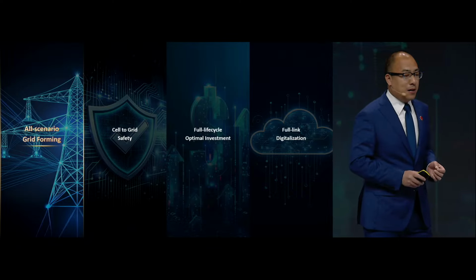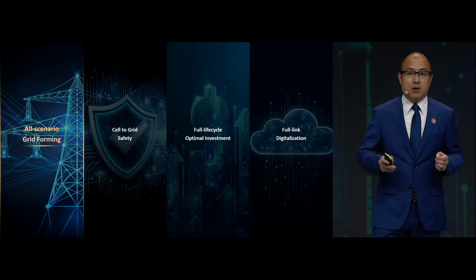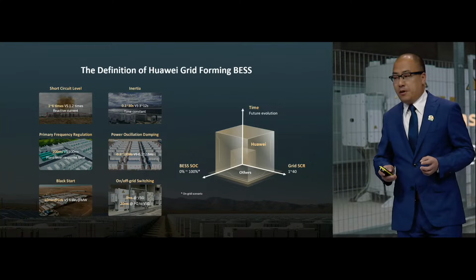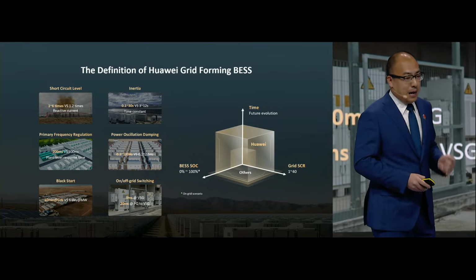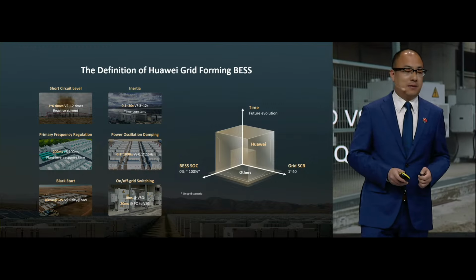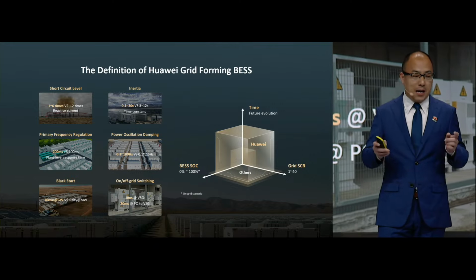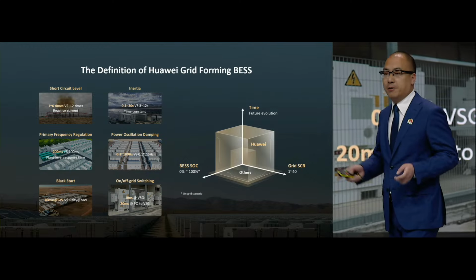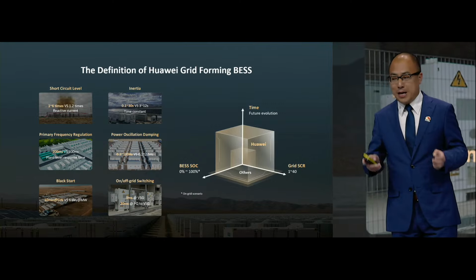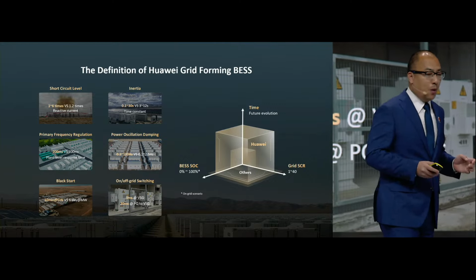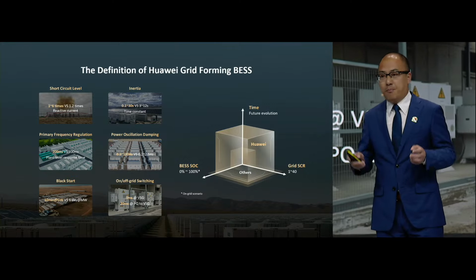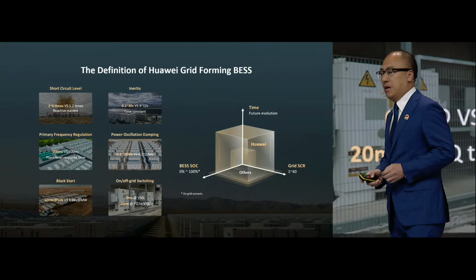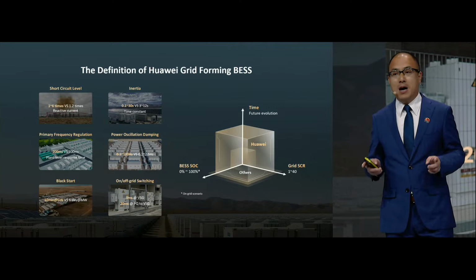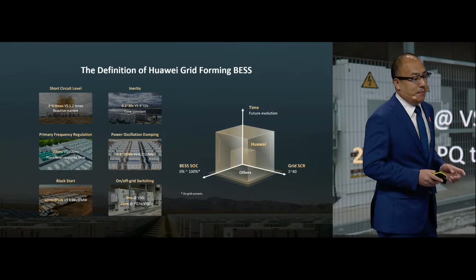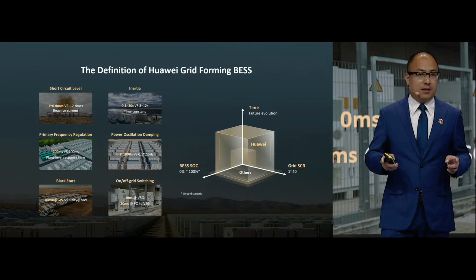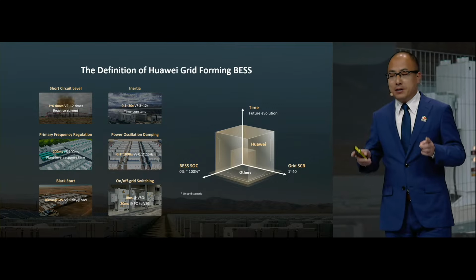The first core capability of the Smart String grid-forming energy storage platform is all-scenario grid-forming. As a key technology for new power systems, we defined 6 capabilities for Huawei grid-forming plant-level BESS. Short-circuit level: support flexible configuration of 1 to 6 times reactive current. Inertia: support 0 to 20 seconds time constant. Primary frequency regulation: the response time at plant level is less than 200 milliseconds. Power oscillation damping: support 0.1 Hz to 100 Hz. And also black start, gigawatt level within 10 minutes. And on-off grid seamless switching also.